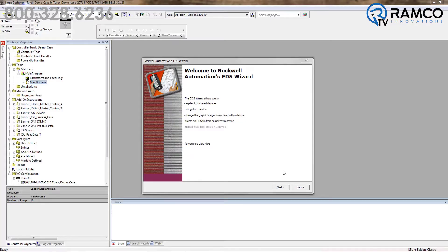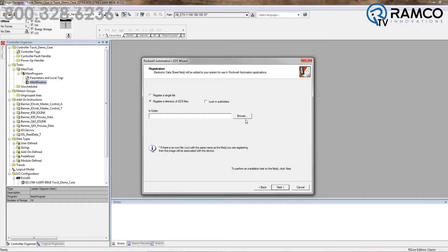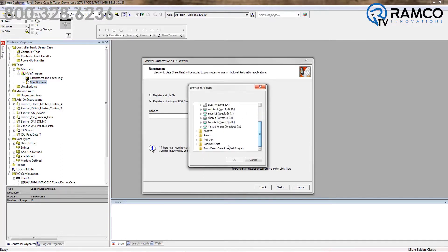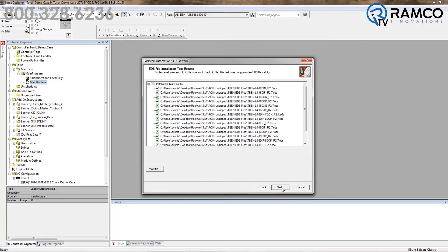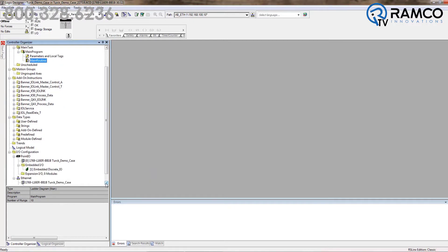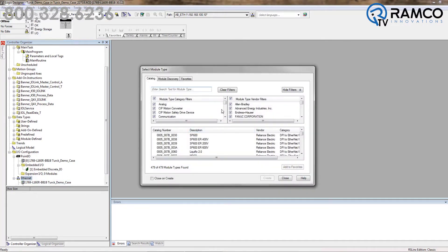Next, we need to get the IO block talking to your PLC. Using the EDS import tool, import the EDS file for your specific IO block. In the description below, you can find a link to download the available EDS files for the IO-Link blocks. Once the EDS files have been installed, go to your Studio 5000 software and right-click on Ethernet and select New Module. Then choose the Turck block.